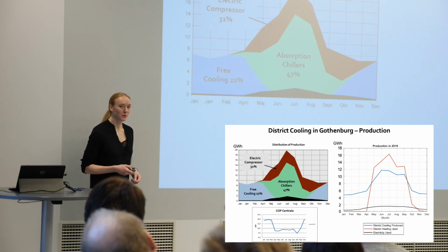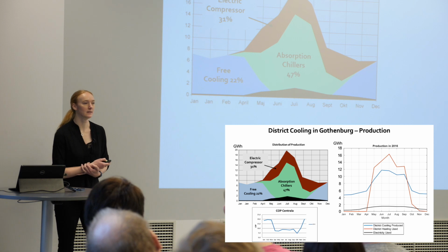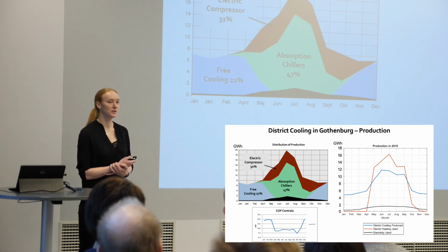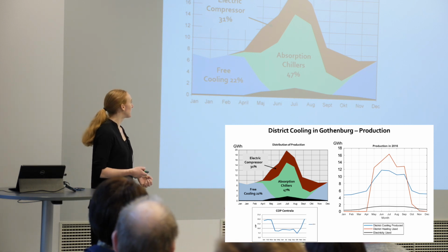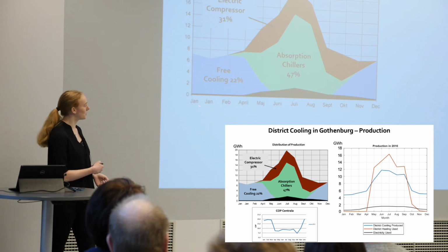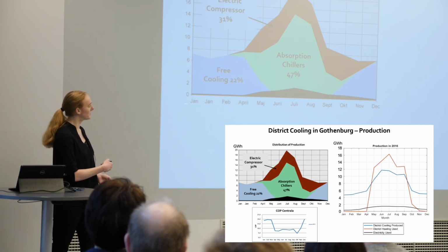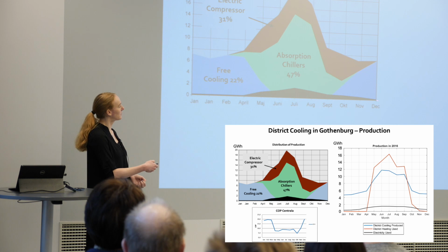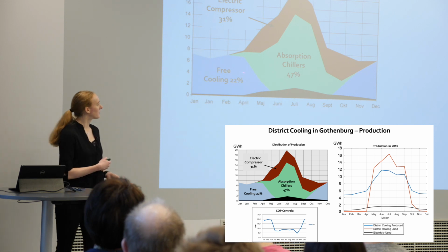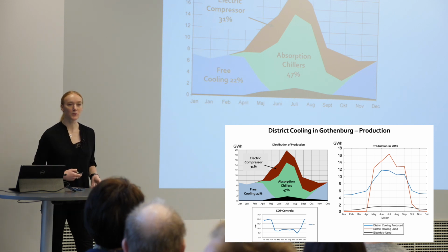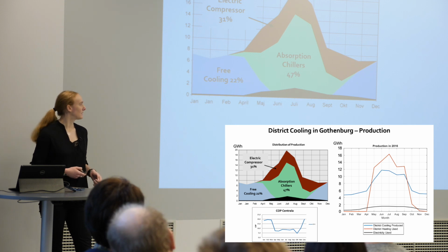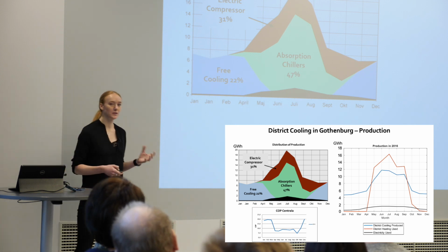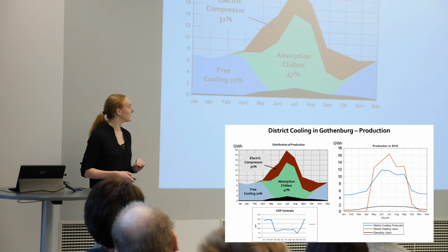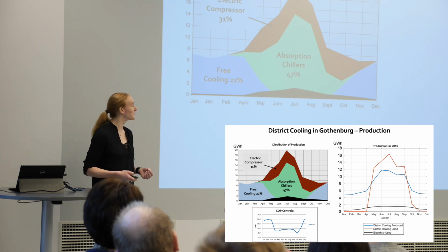So this is what the production mix looks like in the Gothenburg district cooling system throughout the year. And as you can see here, during the cold months in the winter and also in the beginning of winter in December, the river is used to produce the cooling. And the total share of free cooling is around 22% in the whole system, depending on the temperatures of the river.